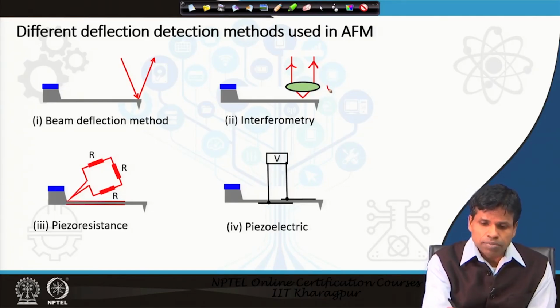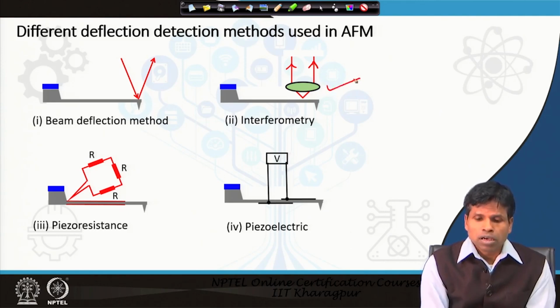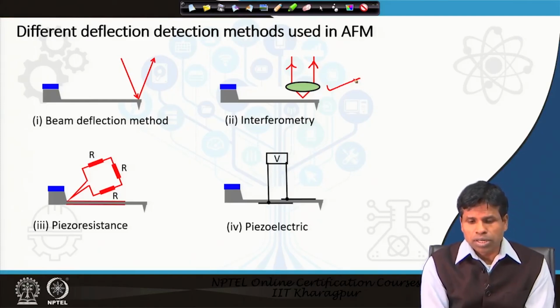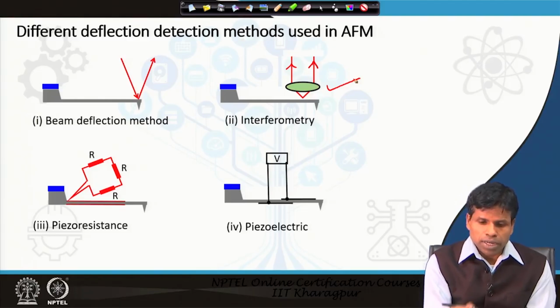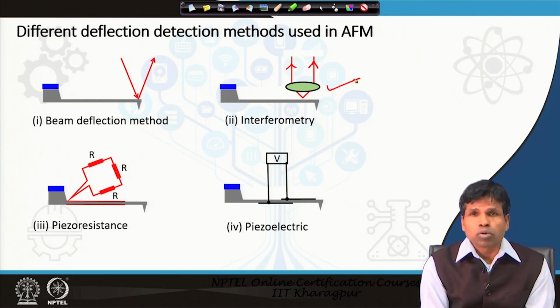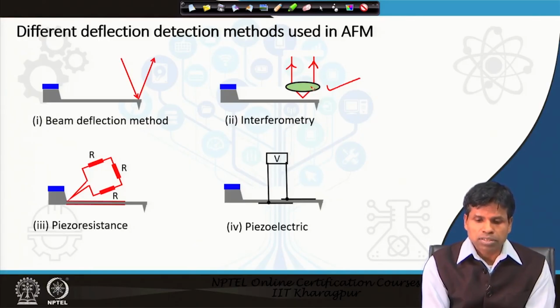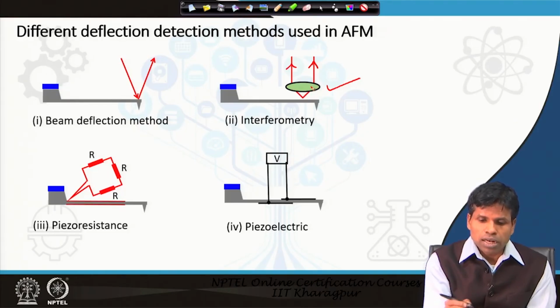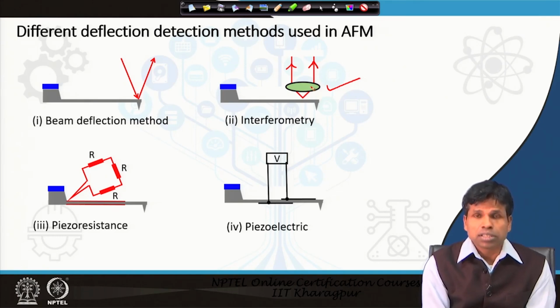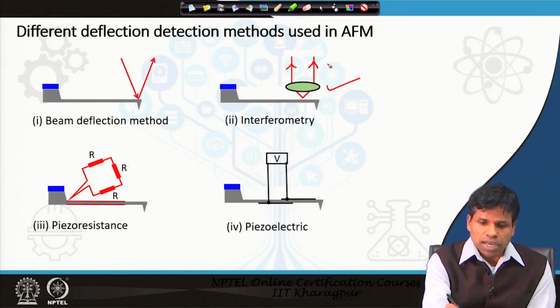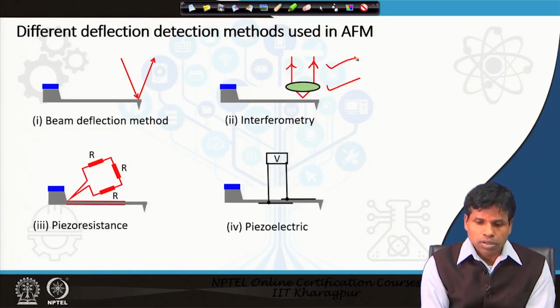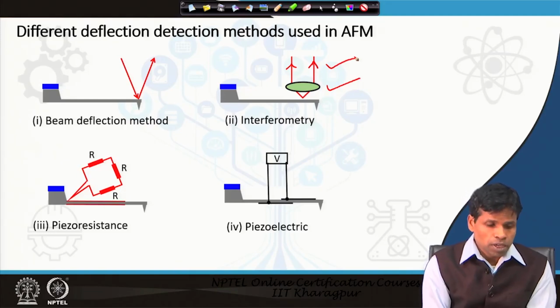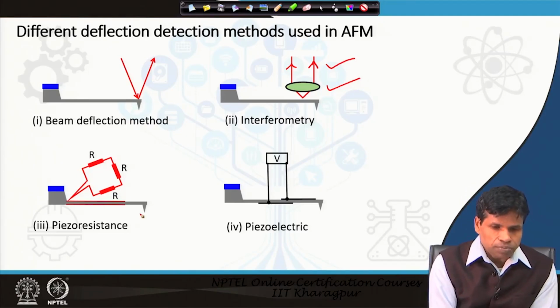It is a very highly sensitive detection process, but the instrumentation is a little complicated, therefore it is not very commonly used in AFM. Moreover, here the calibration is very accurate, because the position can be detected by changing the wavelength of the light that is reflected from the back side of the cantilever. So, as far as preciseness and accuracy are concerned, it is very highly sensitive. On the other hand, the instrumentation is complicated. We also have a piezo resistance detection method.